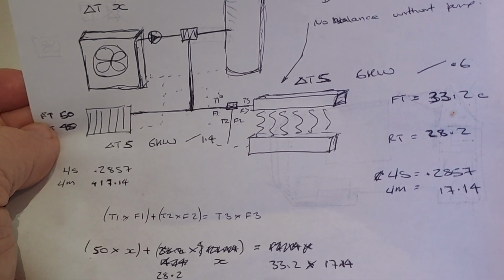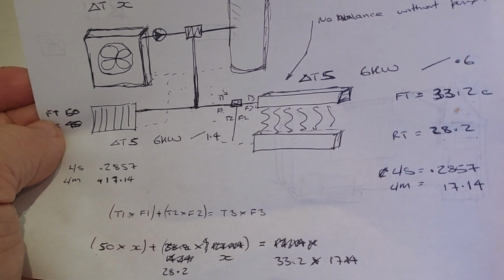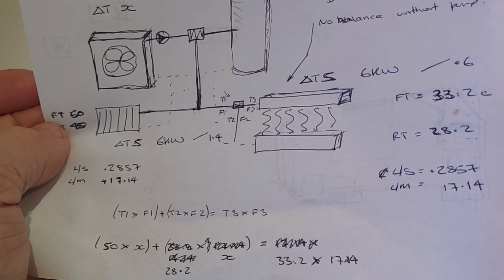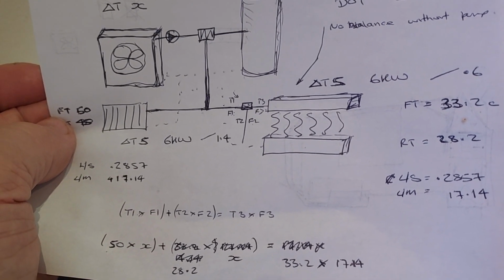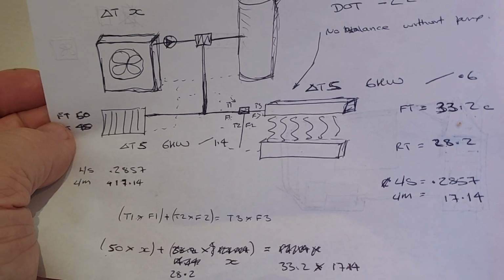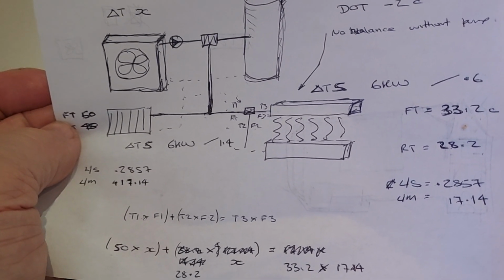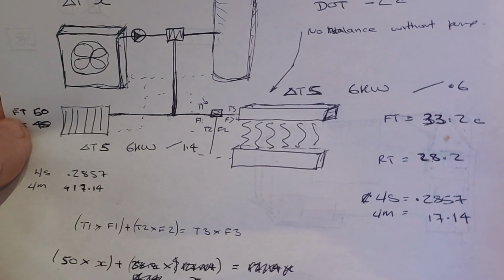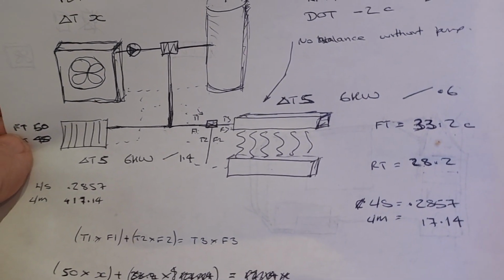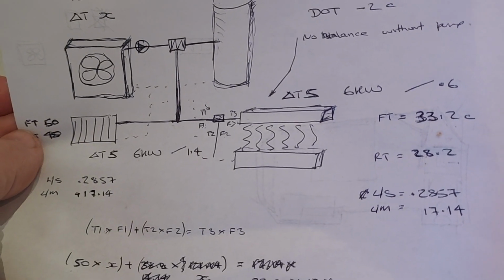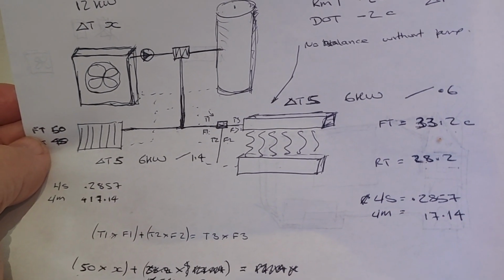The government are recommending a design temperature of 55, so it's under the government's specified design temperature. And it's a very normal curve we find in existing radiators. And then I've gone for underfloor, and I've picked a system of underfloor that's been well installed, so it has a low curve of 0.6. I've done it deliberately to exaggerate the equation to prove a point.